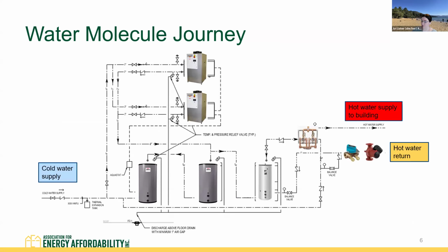So now I'm going to take our molecule of water. We come in on the cold water supply. The first thing is the piping branches up and goes over to the heat pumps. At the heat pumps, this water is heated from supply temperature, usually 50 or 60 degrees, in a single pass, all the way up to 140 degrees, very hot water. Then from the heat pumps, that hot water is delivered to the very top of this first storage tank. This is our primary storage. As the heat pumps are running, they charge hot water through to the bottom of this first storage tank, and then continuing in this piping in series over to the top of the second storage tank. And finally, once hot water is charged at 140 degrees all the way down to the bottom here, a signal is sent to turn off the heat pumps.